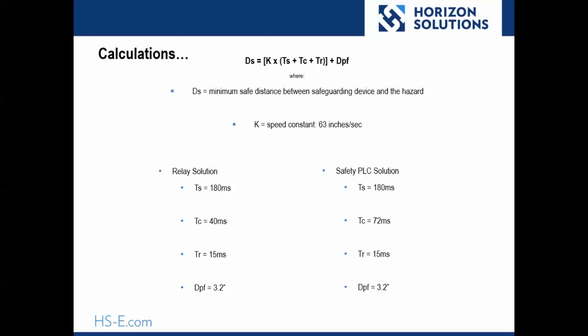For this example, we are using a 15 millisecond reaction time, TR, for the light curtain. The depth penetration factor was calculated using ANSI standards. This will be the same for both situations.